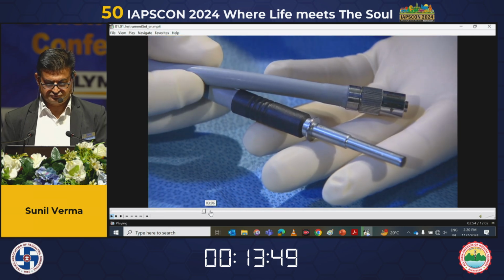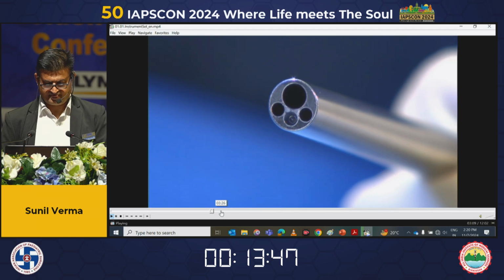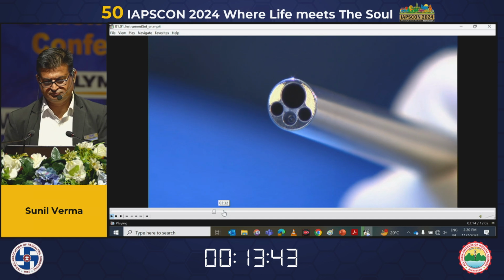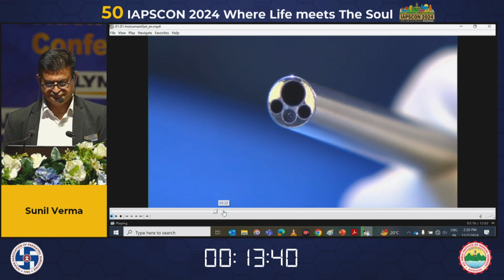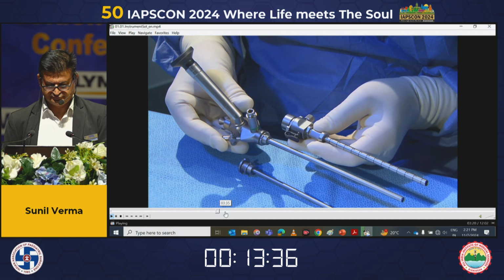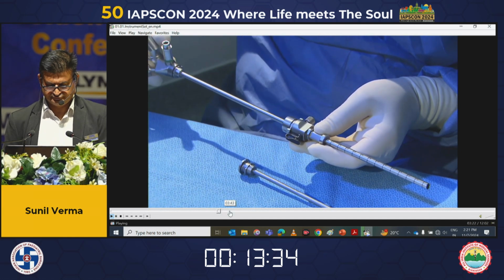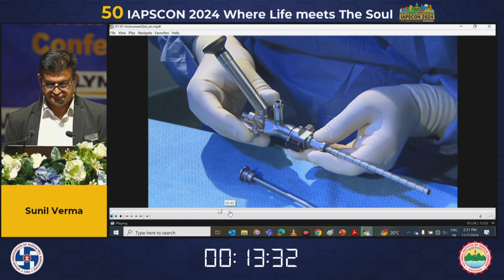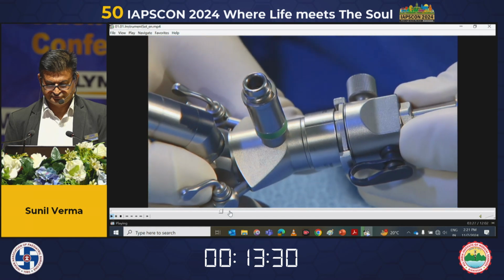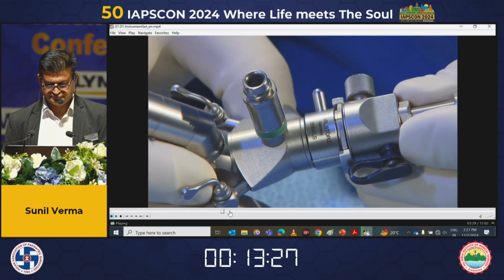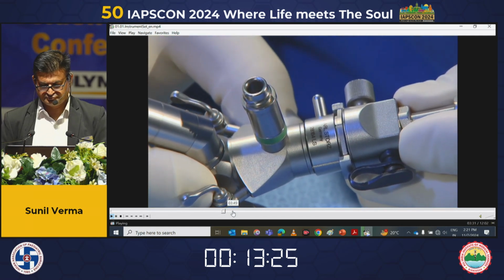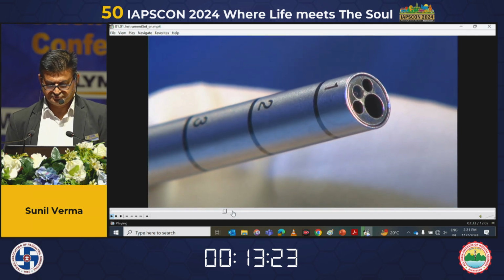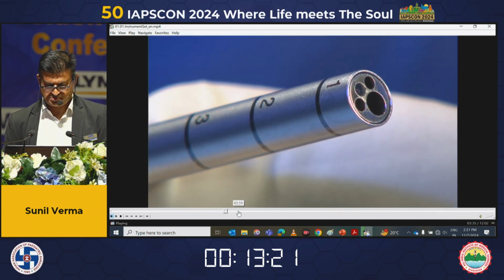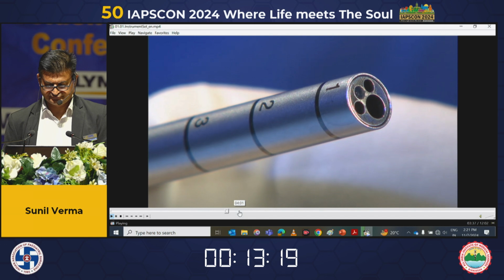The connection for the fiber. To achieve optimal illumination of the surgical field, the optical fibers are arranged circularly around the working channel. After removing the obturator, the ventriculoscope is inserted into the endoscope sheath and fixed into place in the sheath by rotating the locking mechanism. Once the endoscope has been locked in the sheath, the tip of the endoscope is positioned precisely at the tip of the working sheath.